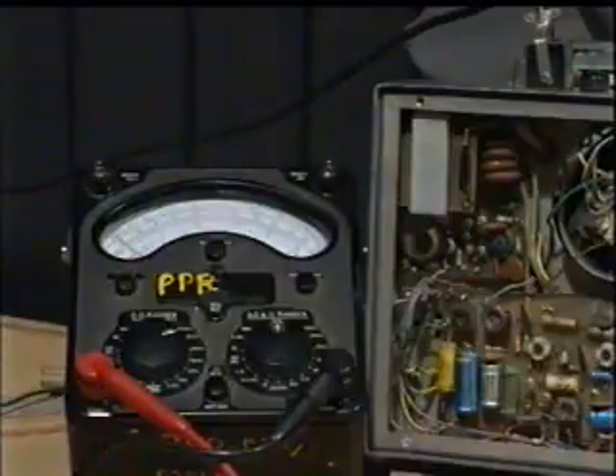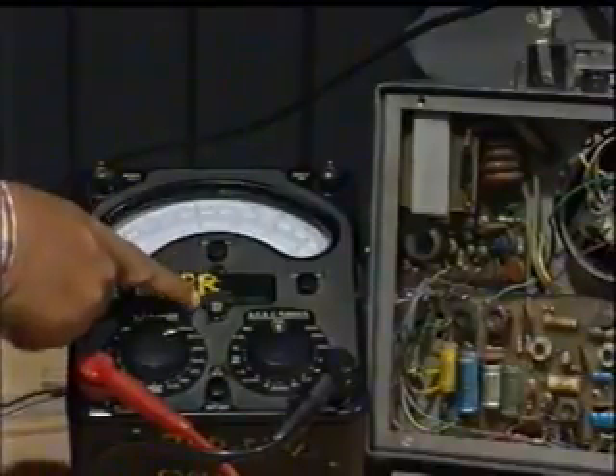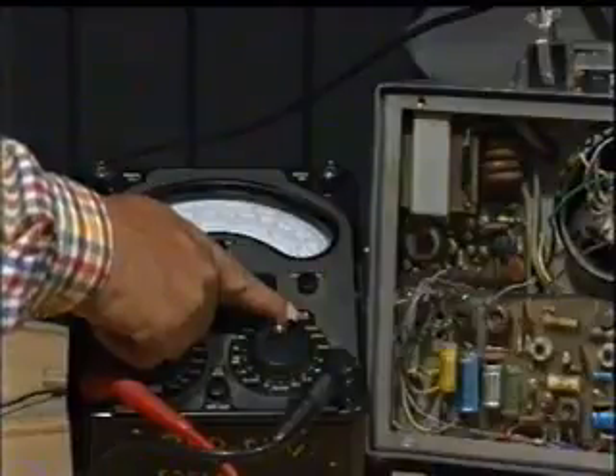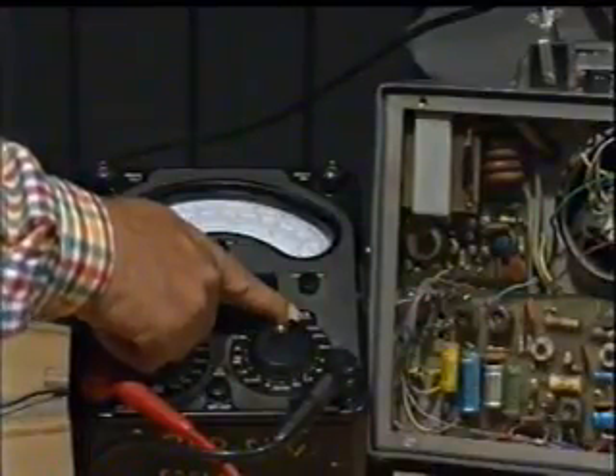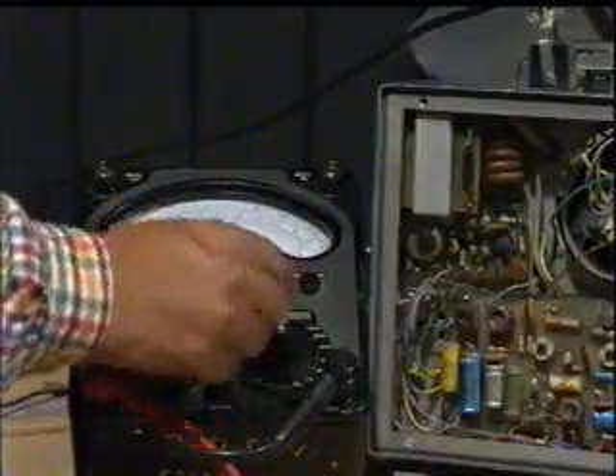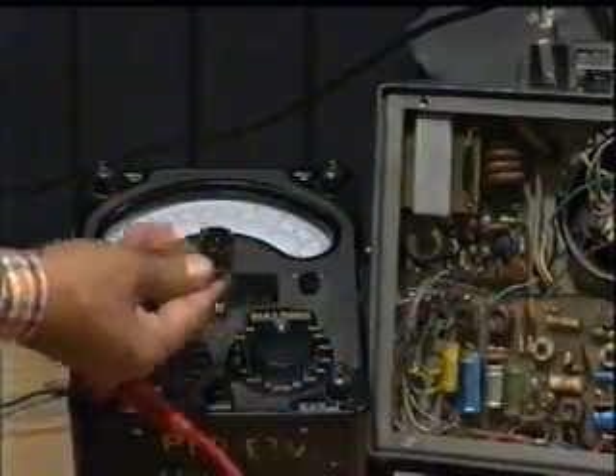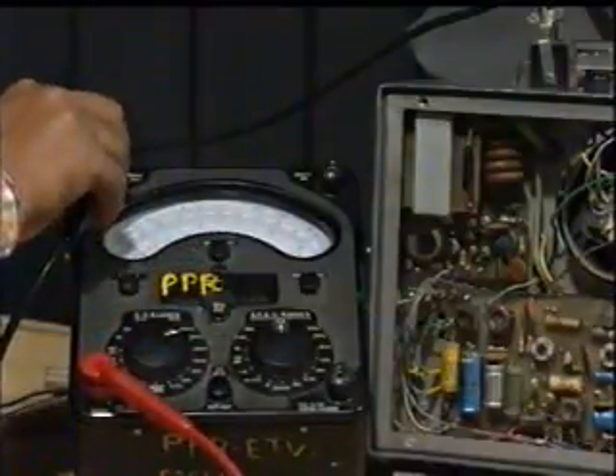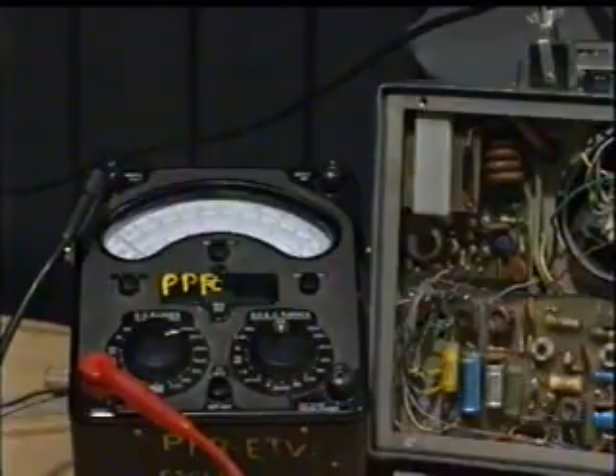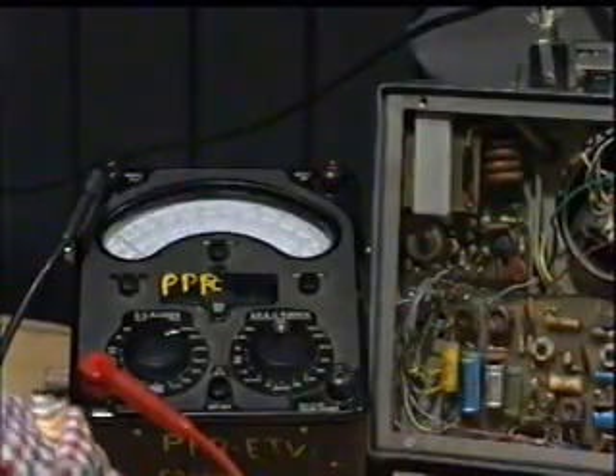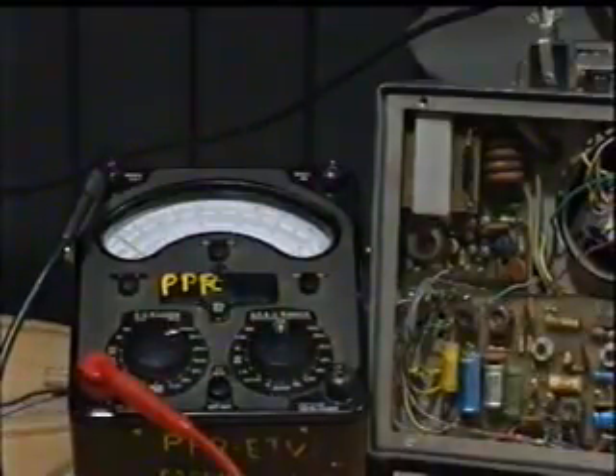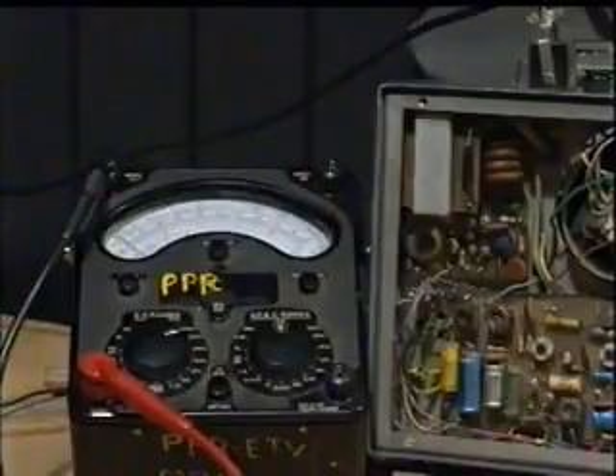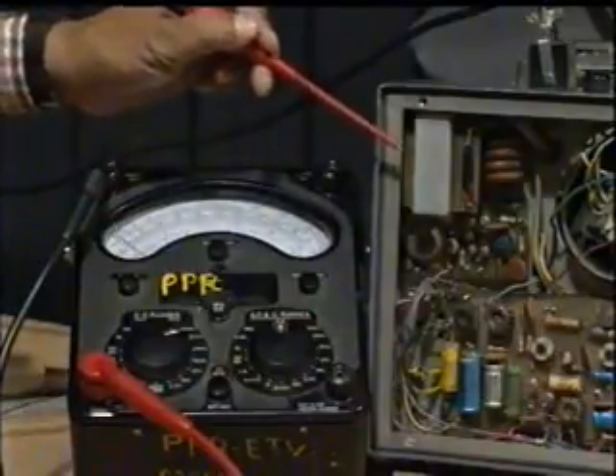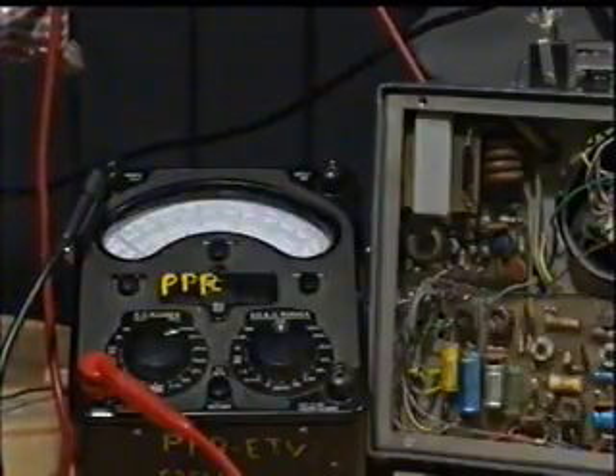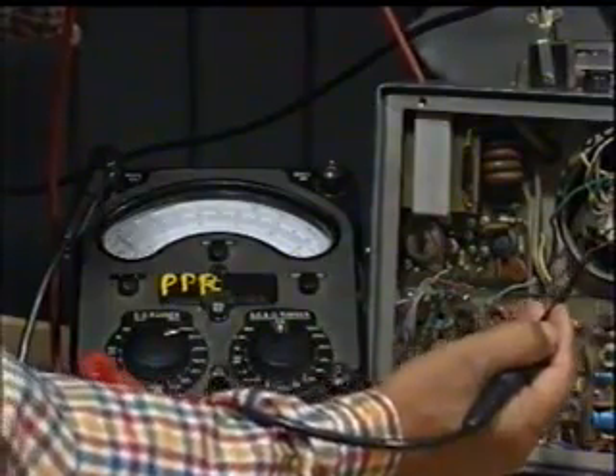Grid and the cathode both have voltage more than 1000 volt, while the range of this multimeter is only 1000 volt to read DC voltages. To read more than 1000 volt, connect lead at proper place to read more than 1000 DC volt. Let us measure the grid and cathode potential. Since we have to measure the negative voltage, put this positive lead on the chassis and the negative lead at pin number 1.